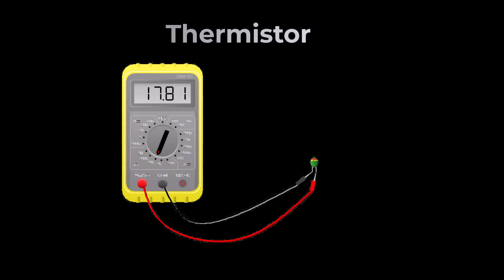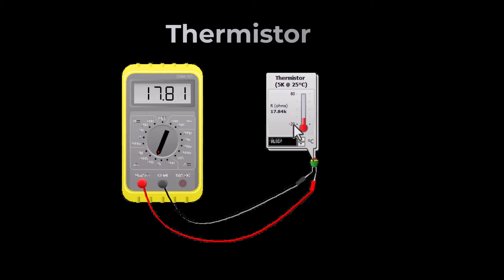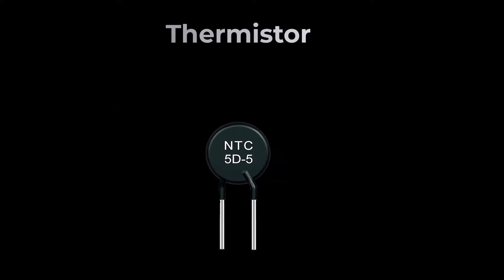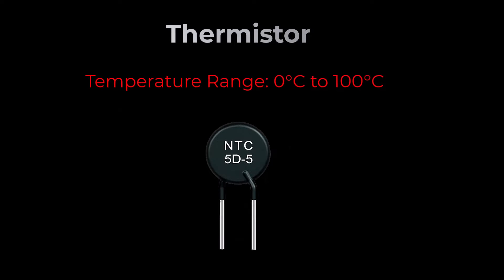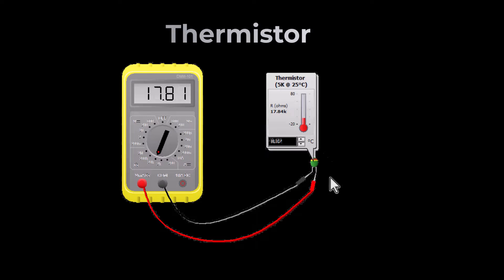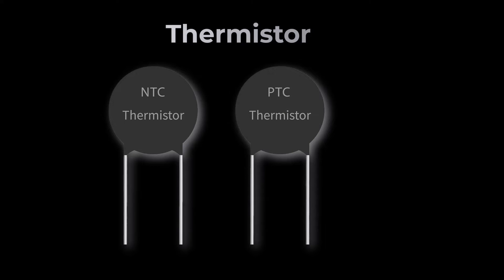Next, the thermistor — small yet mighty, with significant resistance changes. They find their home in medical devices and climate control systems. A thermistor, short for thermal resistor, is a type of temperature sensor that exhibits a significant change in electrical resistance with a change in temperature. Thermistors are known for their sensitivity. The working temperature range for most thermistors is between zero and 100 degrees Celsius. Their resistance changes dramatically with temperature, which distinguishes them from RTDs and thermocouples.